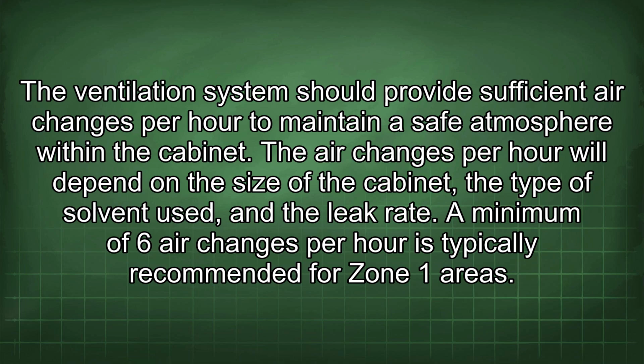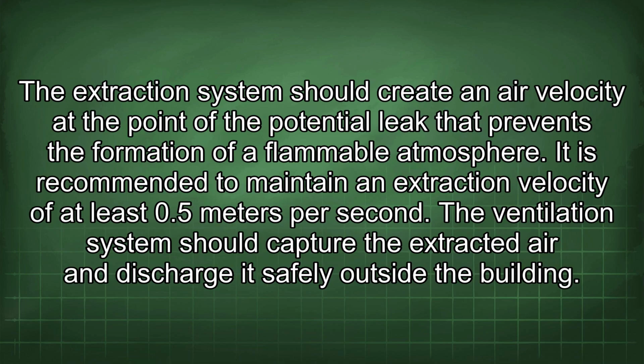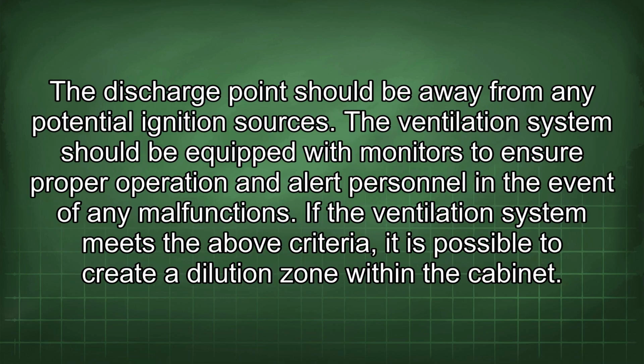The air changes per hour will depend on the size of the cabinet, the type of solvent used, and the leak rate. A minimum of 6 air changes per hour is typically recommended for Zone 1 areas. The extraction system should create an air velocity at the point of the potential leak that prevents the formation of a flammable atmosphere. It is recommended to maintain an extraction velocity of at least 0.5 meters per second. The ventilation system should capture the extracted air and discharge it safely outside the building. The discharge point should be away from any potential ignition sources.